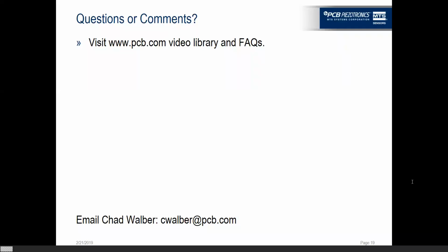First rule is, what frequency range are you actually interested in? Depending on the type of microphone, if it's a half-inch microphone, everything below about half to three-quarters of the resonance is a flat frequency response, meaning it doesn't matter if it's a free field, pressure, or random incidence response. They're all the same right up until about 5 or 6 kilohertz. Furthermore, if you want to use the entire frequency range of the microphone, understand that the field type that you're in will be different than possibly the calibration of your microphone, and be ready to correct for it in your post analysis of your data. So if you know that it's going to be a couple dB off at the higher frequency, understand that you have to correct for that in your data.